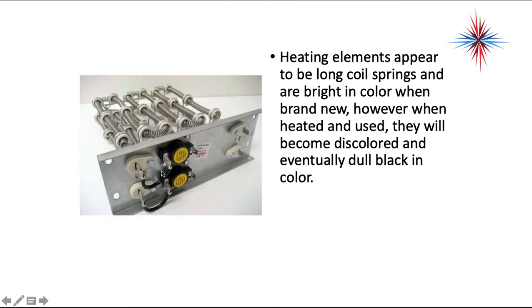And again, when we look at this heat strip that's over here in our picture, this portion with the spring looking material, that's in the airstream. That's the portion that heats up. You'll have 4 screws. This mounts directly into the cabinet of your air handler. You'll connect L2 to both of these terminals. You'll connect L1, one here, one there. And again, how you wire it is dependent on if you want both stages of heat to come on at the same time.